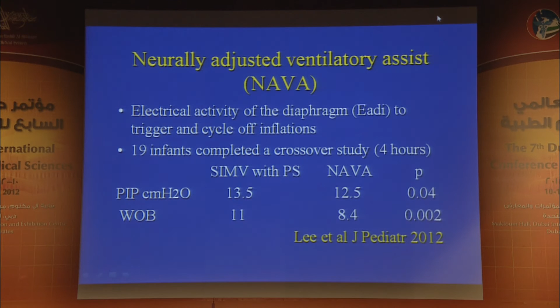Now, for those of you not familiar with NAVA, what happens is there is a catheter pushed down, which is a nasogastric tube, on which there is a montage to detect the EMG signal of the diaphragm, and the montage sits above and below the diaphragm. And so as the baby makes inspiratory efforts, the EMG signal is used to trigger the ventilator. And so this work of breathing is lower because it absolutely, faithfully maps on to what the infant's respiratory efforts are doing.